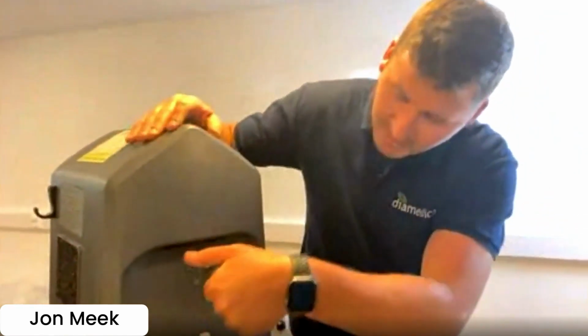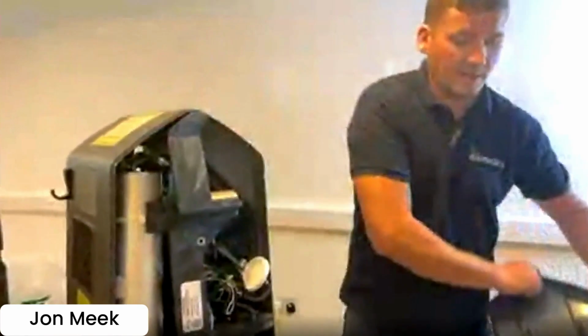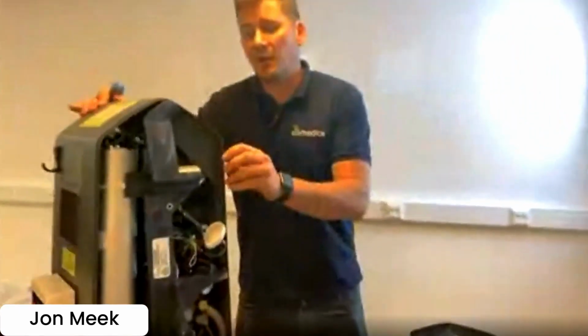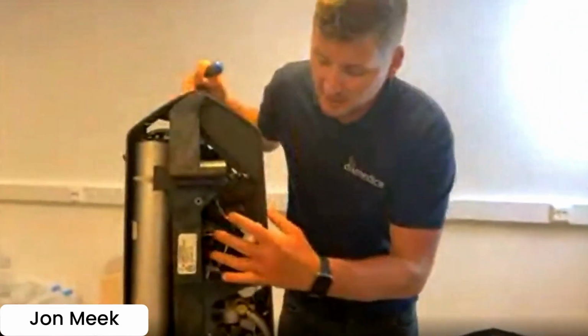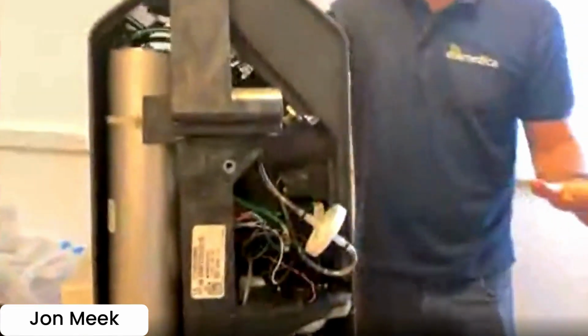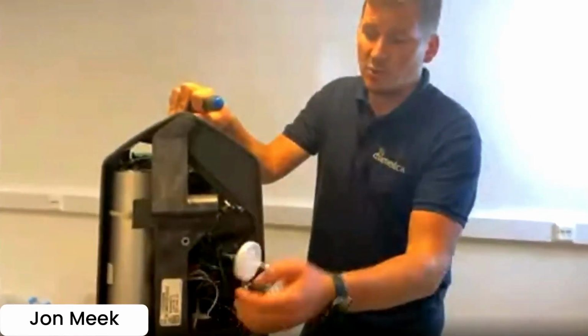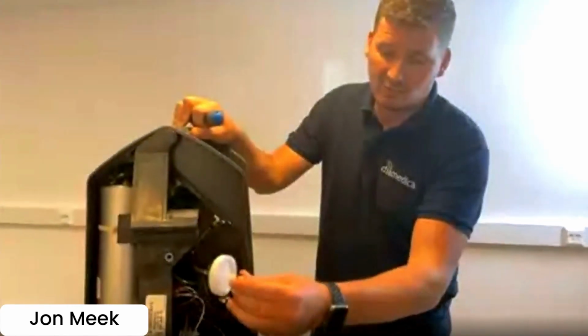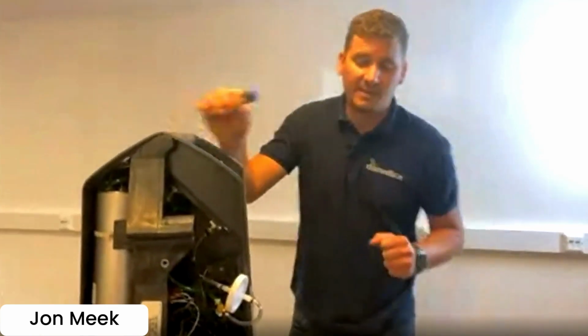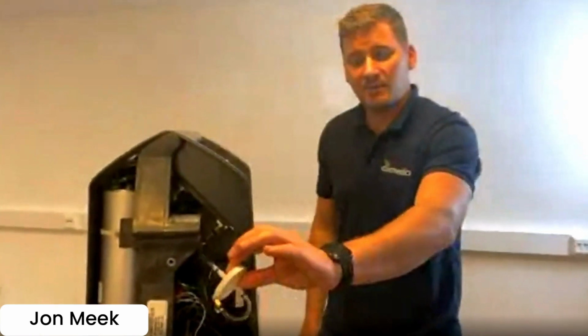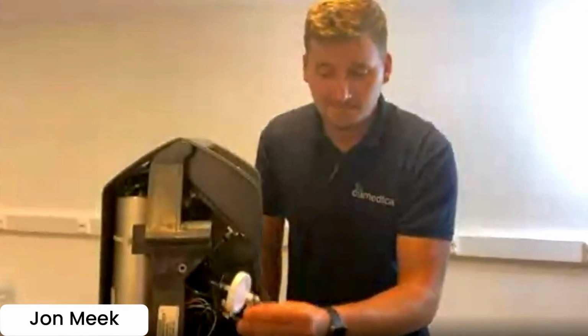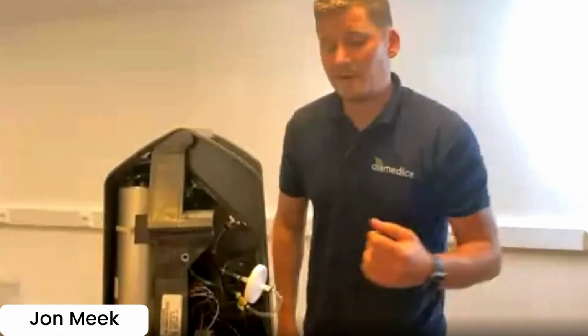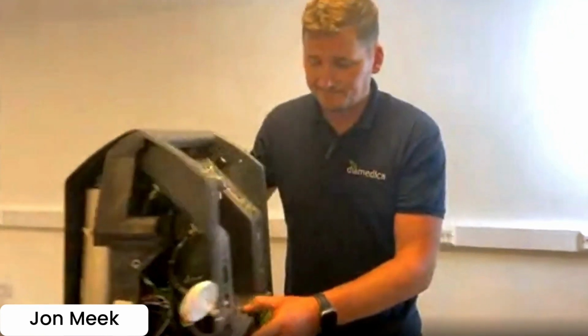In the option side, again, we used to have different flow regulators in this side. We now do not have any flow regulators because you don't want to control the flow. It's all controlled now from the pressure being derived inside, which is 20 psi. We still have a HEPA filter for any final bacteria filter going back to the patient. You want to make sure we had a HEPA filter to make sure it's clean and functioning correctly.